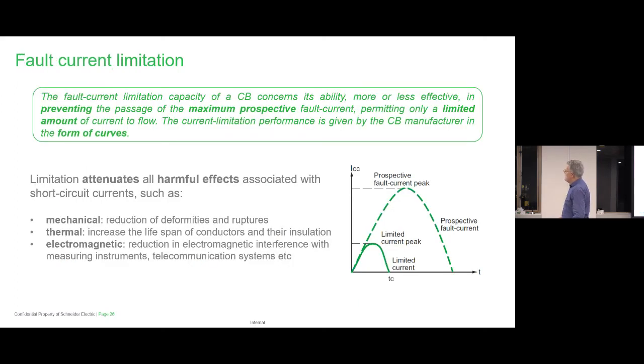Now this brings us to fault current limitation. Fault current limitation is what the circuit breaker is doing. It's limiting the fault. That's what we want it to do. And what is a fault limiting breaker? Well, most of the time it's the moulded case circuit breaker. Sometimes it's the miniature, some of those larger miniature breakers.